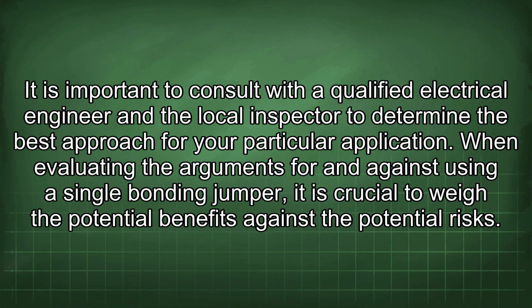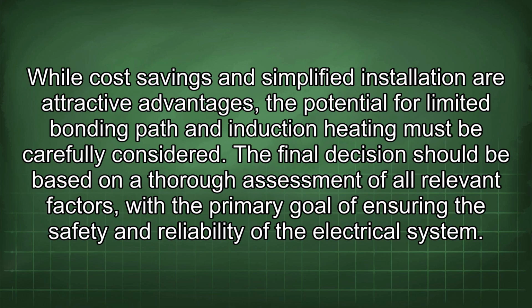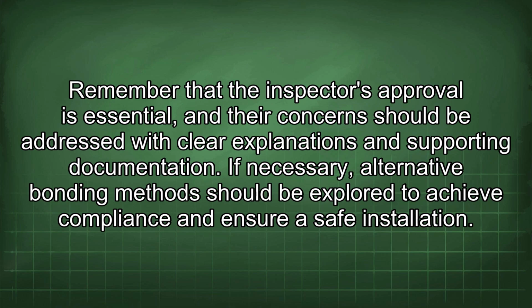When evaluating the arguments for and against using a single bonding jumper, it is crucial to weigh the potential benefits against the potential risks. While cost savings and simplified installation are attractive advantages, the potential for limited bonding path and induction heating must be carefully considered. Final decisions should be based on a thorough assessment of all relevant factors, with the primary goal of ensuring the safety and reliability of the electrical system. Remember that the inspector's approval is essential, and their concerns should be addressed with clear explanations and supporting documentation. If necessary, alternative bonding methods should be explored to achieve compliance and ensure a safe installation.